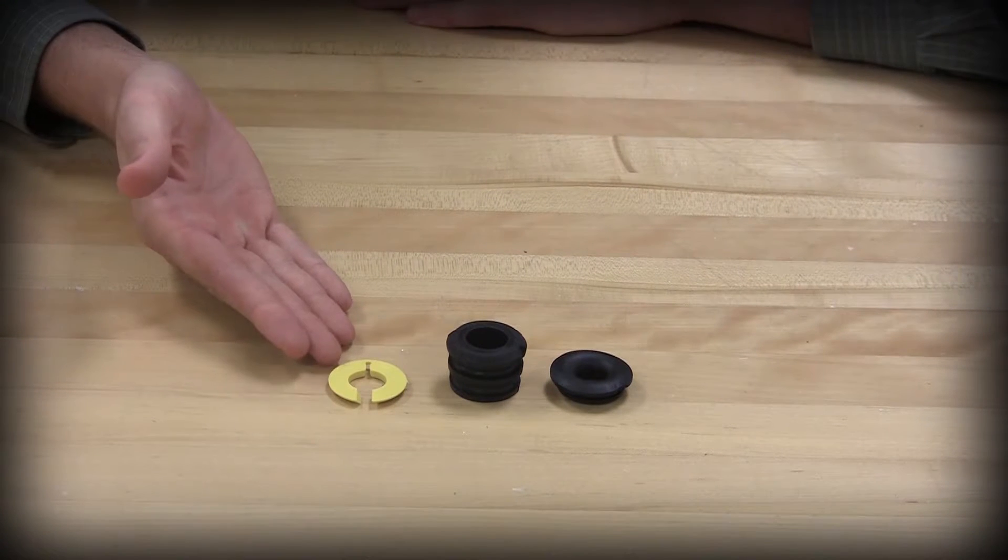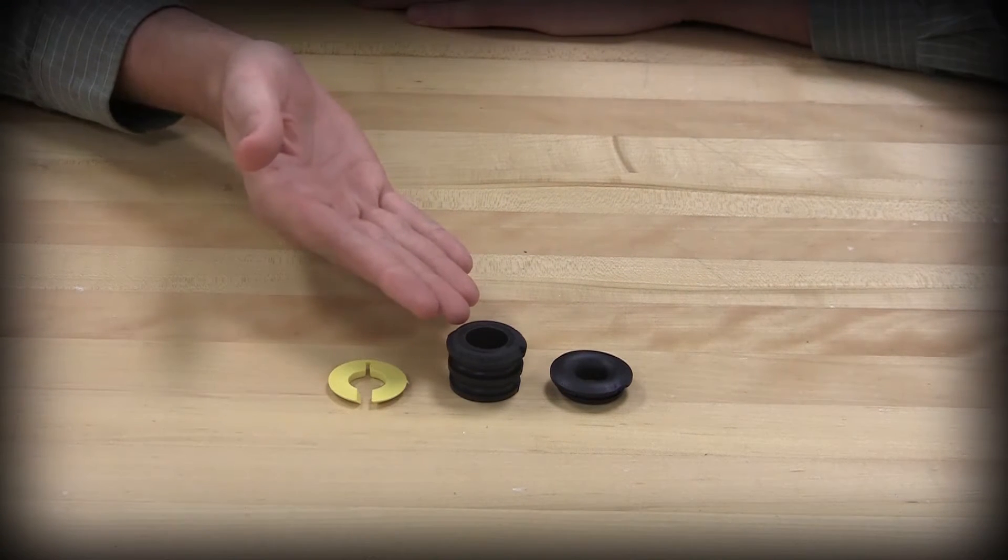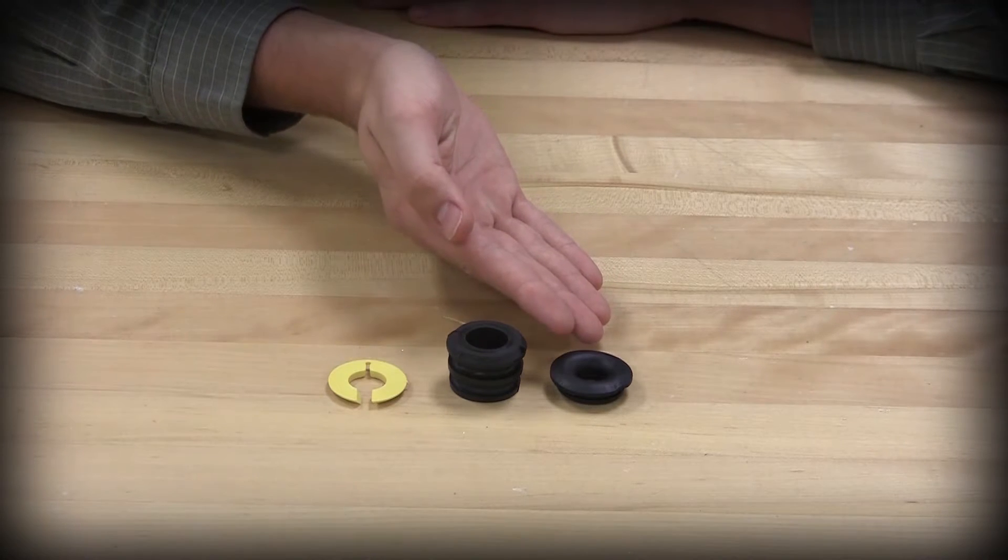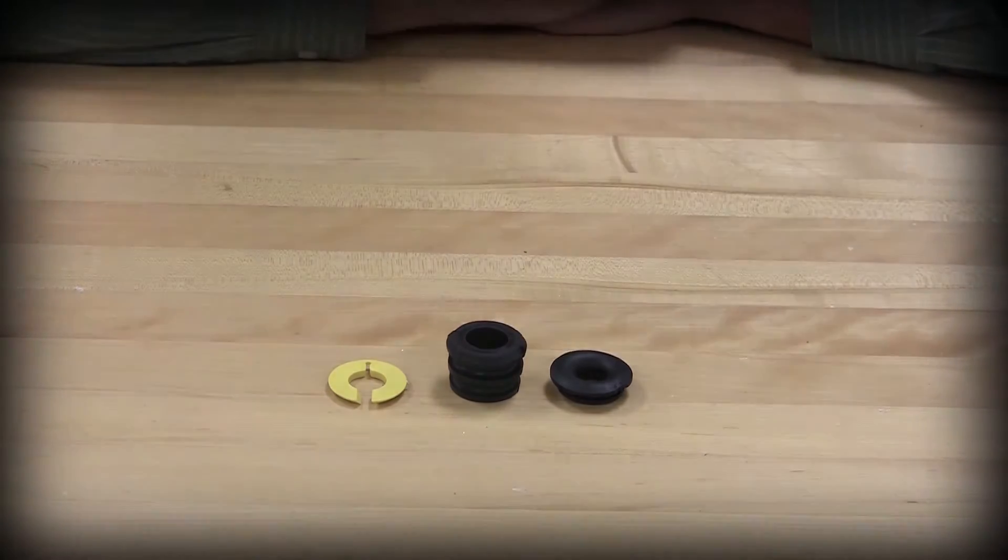The gotcha ring provides strain relief, the rubber bushing also provides strain relief and some sealing around the cable, and the cone seal prevents water and debris from entering the back of the device.